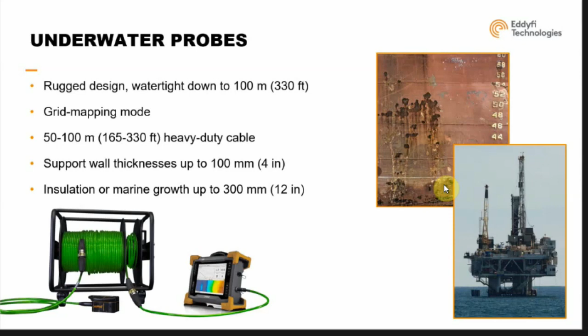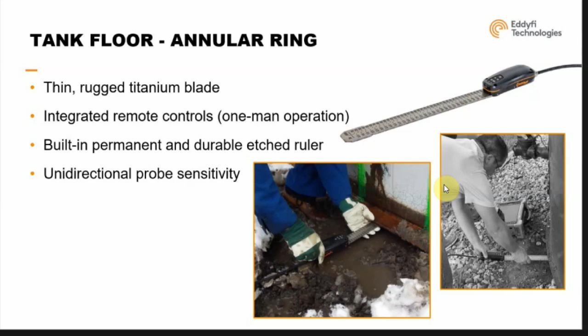A very specific application: it always has been a challenge to measure or detect corrosion at this specific location in a reservoir, in a tank. Provided you can access below the annular plate with a titanium probe, which is covering 400 millimeter, you can try to insert your probe underneath the annular plate and detect corrosion, and get an idea of the damage by sizing the remaining wall thickness.